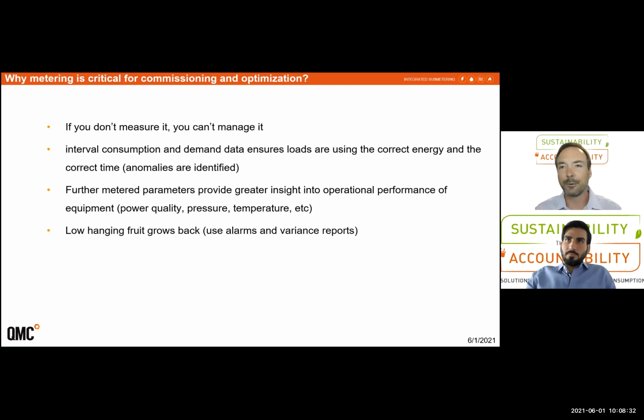And of equal importance is once you've commissioned the system, you make sure everything's running. I like the adage that low-hanging fruit grows back. You can obviously find those anomalies with systems, but you need to keep on top of it, because a year or two down the road, the inefficiencies in systems can come back, and you want a good meter system to catch that.